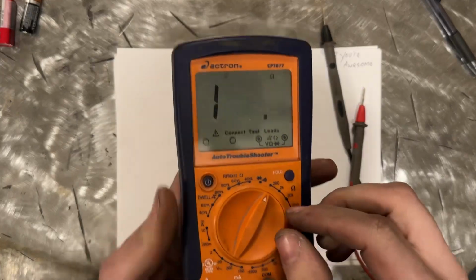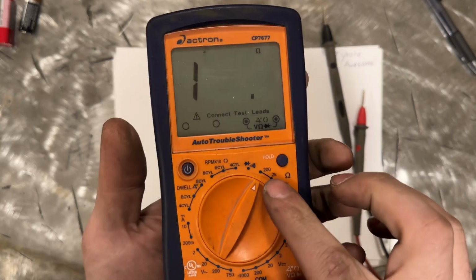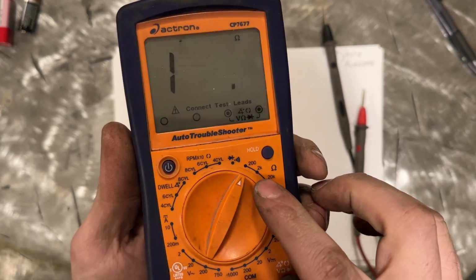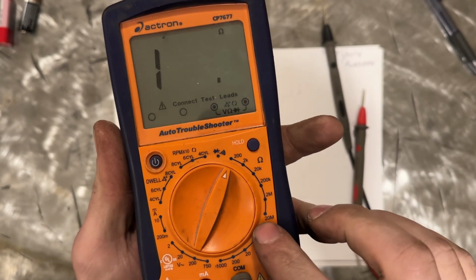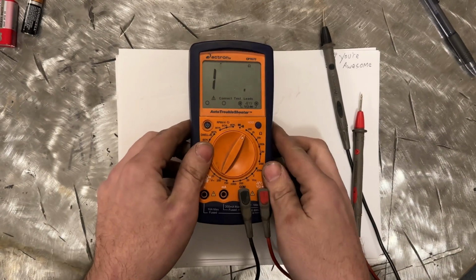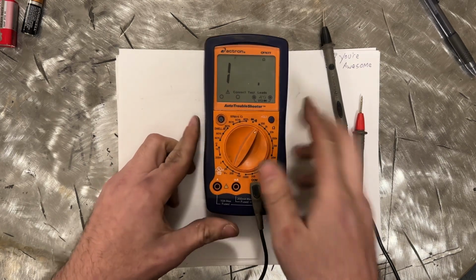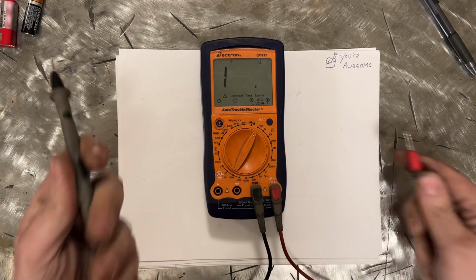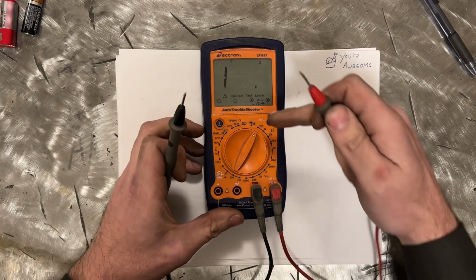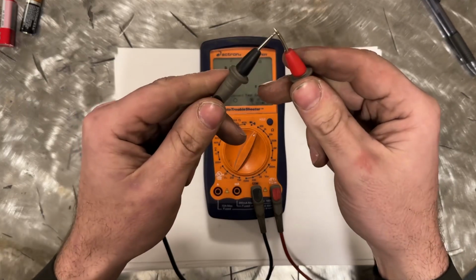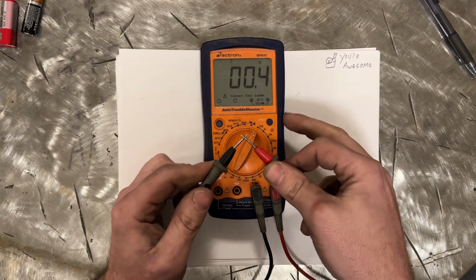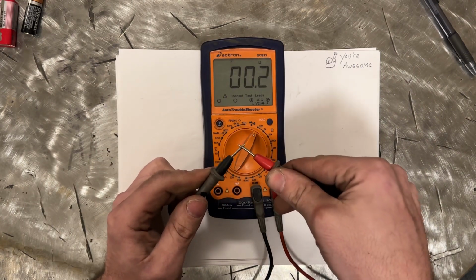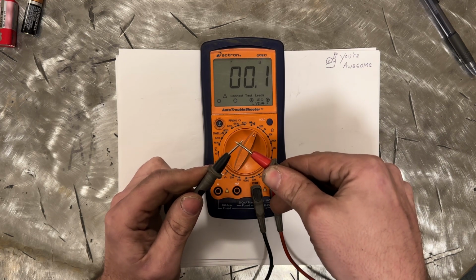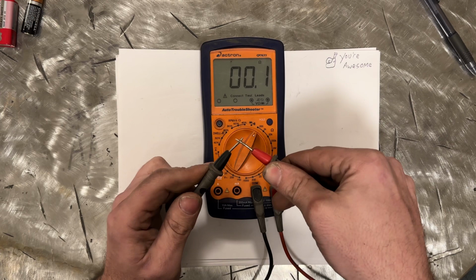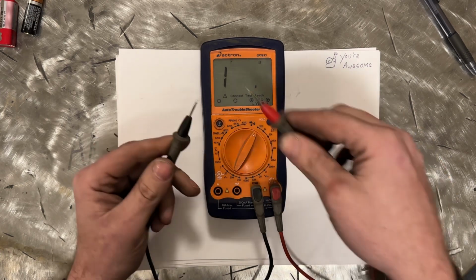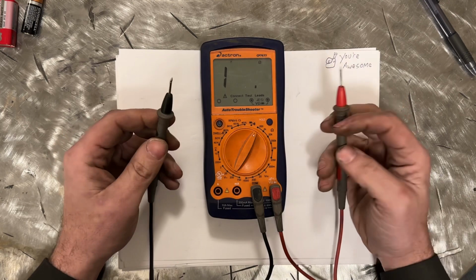All right, let's talk about ohm testing. So this meter I have set for 200 ohms. It goes from 200 all the way up to 20 million. Now for ohm testing, if you're looking for a short, it's a great way to test for it. The first thing you want to do when you have your leads hooked up, just like for voltage testing, is touch them together and make sure that the reading is low. So right now it's 0.2, probably 0.1. Yeah, it goes down to 0.1. That means we have continuity or very low resistance between these two wires in the meter.